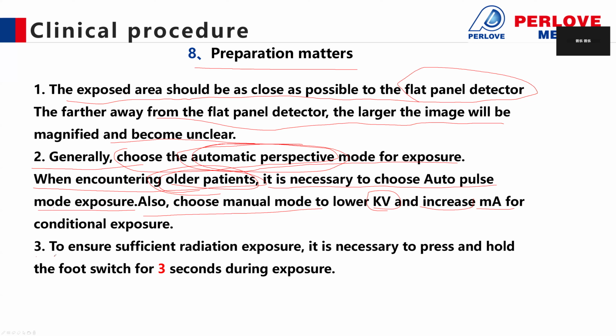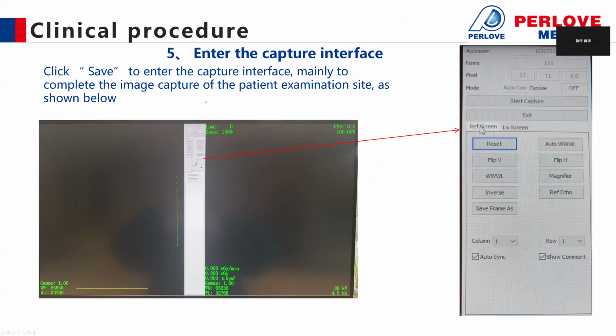And finally, to ensure sufficient radiation exposure, it is necessary to press and hold the foot switch for 3 seconds during exposure. So when you want to expose, you need to press the foot switch for 3 seconds. Here is some information that we need to know before we expose. And the next picture is the capture interface.